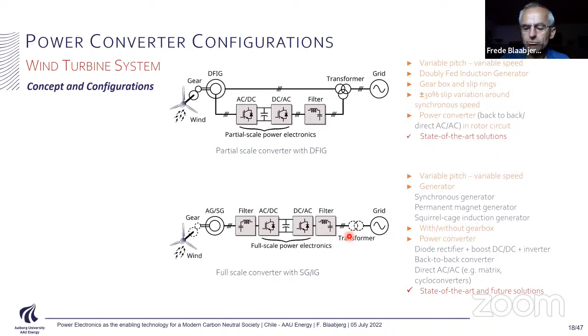The alternative is this one here, where we have a three-phase generator. Then we, to the right, have the grid. And here we do AC to DC conversion, where we convert the full power. And here we do DC to AC conversion, where we also convert the full power in order to feed the power into the grid. But this has the clear advantage that we can decouple almost the two systems. So if something happens at the generator, we can decouple the grid, and opposite, if something happens at the grid, then we can decouple the generator and try to deal with that.